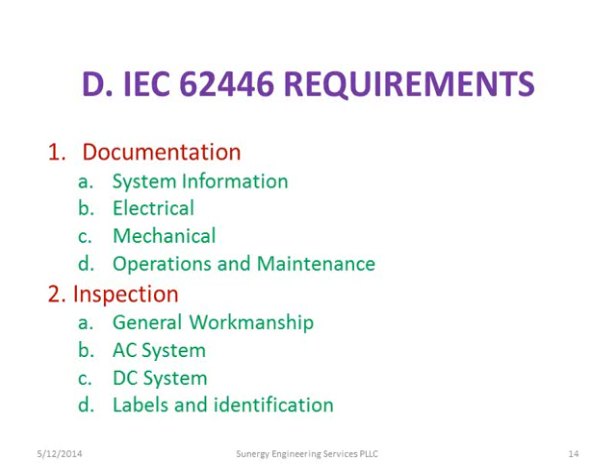But basically, a true full commissioning means you got to go through all the documentation. You got to go through all the electrical single line drawings, 3-line drawings, all the spec sheets. You got to look at all the wire calcs, you got to look at all the overcurrent protection calcs, and you got to check to make sure that that's all been done right before you even go on the site. And then you have to also check all the mechanical, if you had wind loading or other things, or if you just used the racking manufacturer's recommendations for the racking based on your wind loads, that all needs to be documented. And it needs to be documented in a way that the person that's in charge of the operations and the maintenance can find that material, and he can track down all the owners that did different parts of the work, or all the people that supplied the different parts that are used in the system.